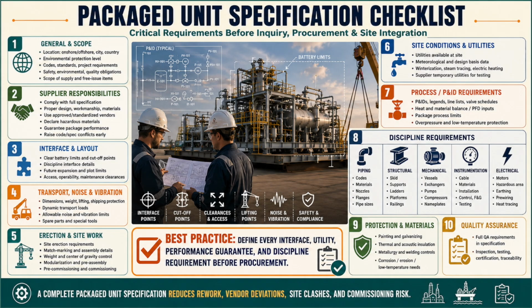The package P&ID must show process limits, isolation points, drains, vents, relief devices, control loops, shutdown functions, utility connections, and interfaces. Overpressure protection must be addressed explicitly. Who sizes the relief valves? Who validates relieving scenarios? Where does the discharge go? Is the package protected against blocked outlet, control valve failure, external fire, thermal expansion, utility failure, and other credible cases?